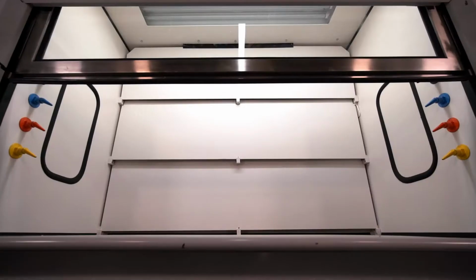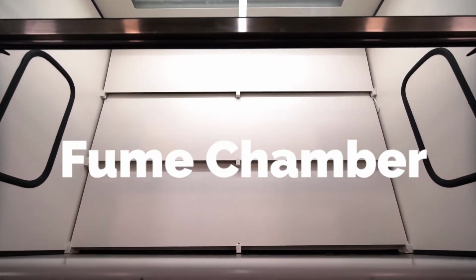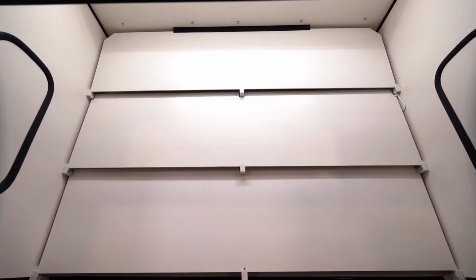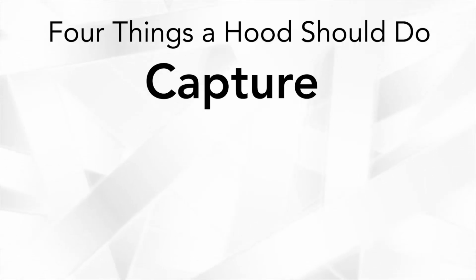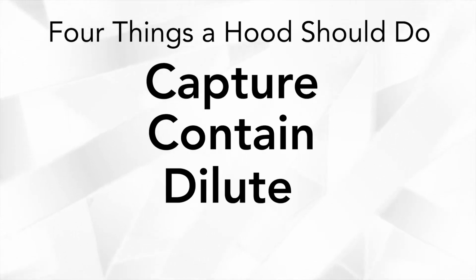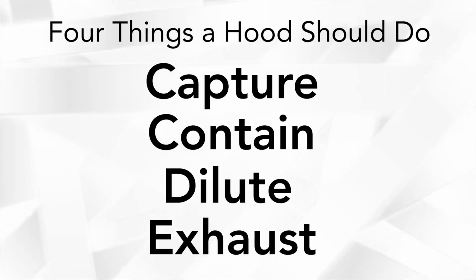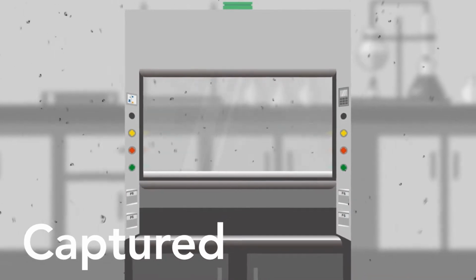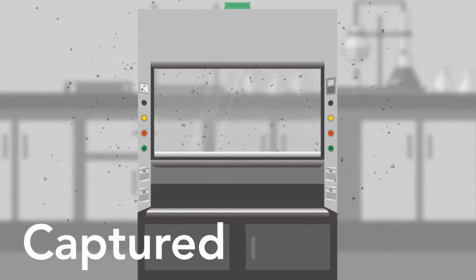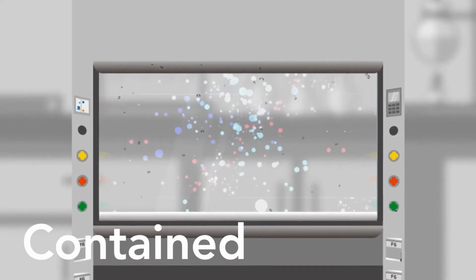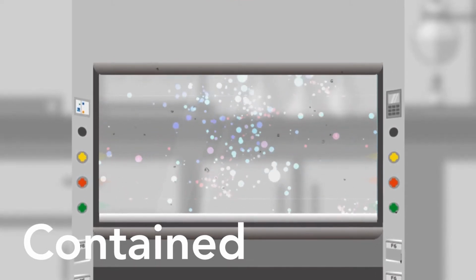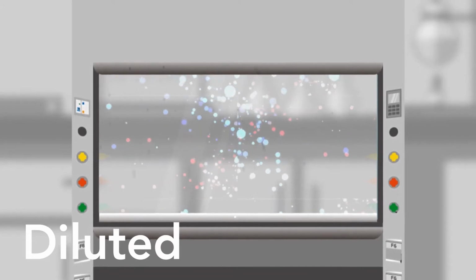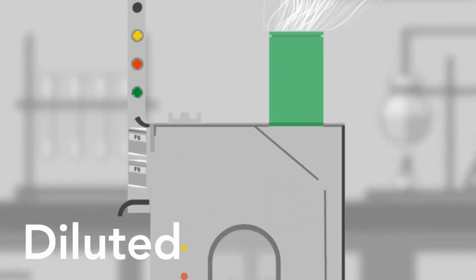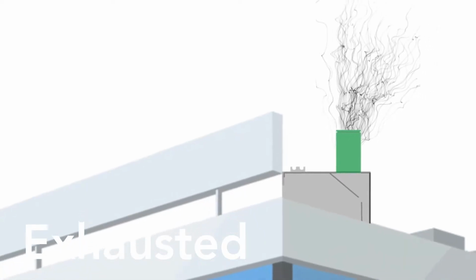The inside of the hood is called the fume chamber. This is where your work is done. Inside the fume chamber, there are 4 things the hood should do: capture, contain, dilute, and exhaust. The fumes, vapors, particles, and mist produced within the fume chamber should be captured. Once captured, they should be contained within the fume chamber and not allowed to escape. While they're in the fume chamber, they should be mixed with air and diluted to a safe level. Once properly diluted, they are then exhausted outside and away from the building.